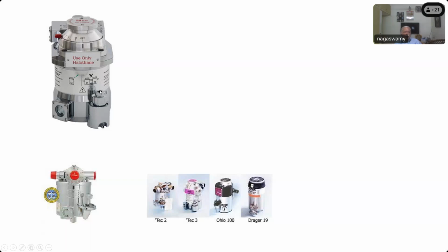And if you invert this, you can see there is a small depression here. And there will be a stem-like thing, like what you see in your anesthesia cylinder, the stem with which you open the gas; some sort of the same stem will be there inside that opening. So you invert this cap and fit it and unscrew that. This hole is for removing the gas. Supposing you want to remove this vaporizer and fix it into some other machine, or you want to keep it empty during the night or weekend when you don't want the vaporizer to be filled with the liquid and left like that.